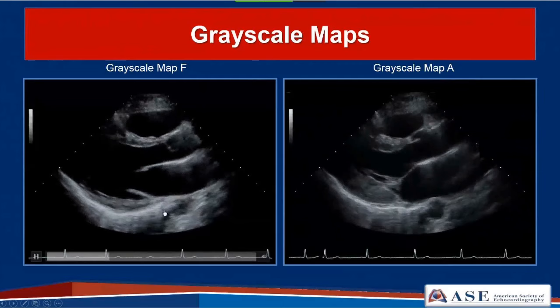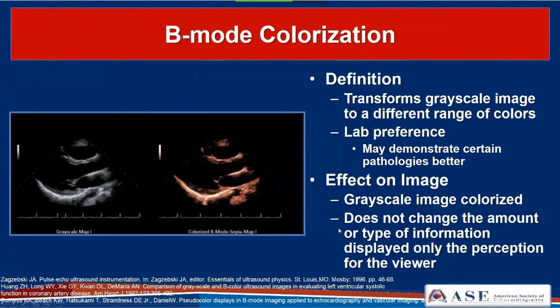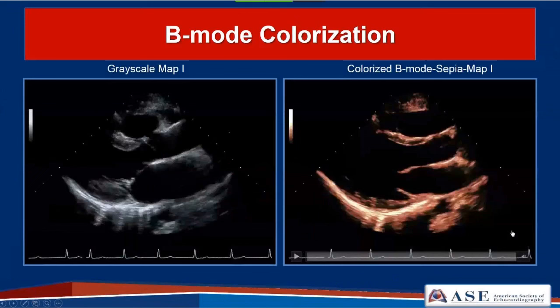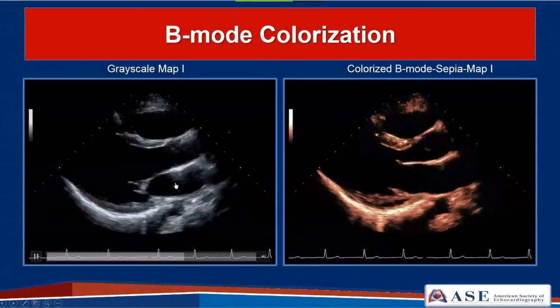B-mode colorization is another tool that transforms the grayscale image to a different range of colors, really based on lab preference. It may demonstrate certain pathologies better and certain interpreting physicians may prefer it for seeing specific pathologies. It does not change the amount or type of information displayed—only the perception for the viewer. For example, colorizing map I to sepia still uses the same map I, just in a different color range.